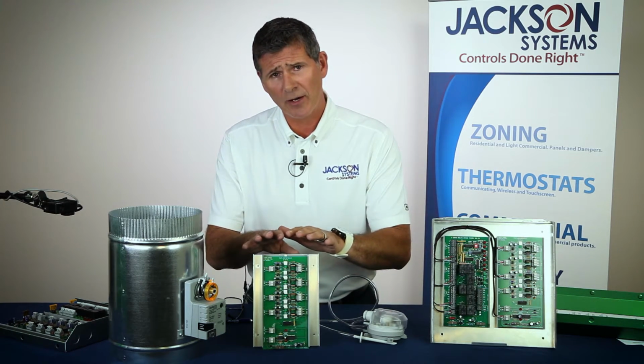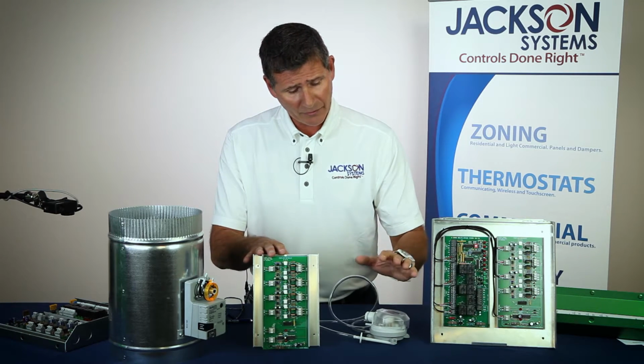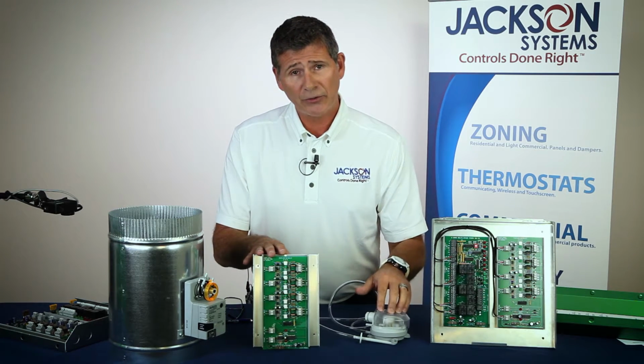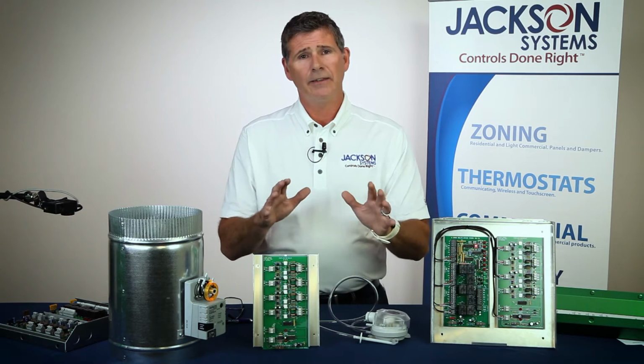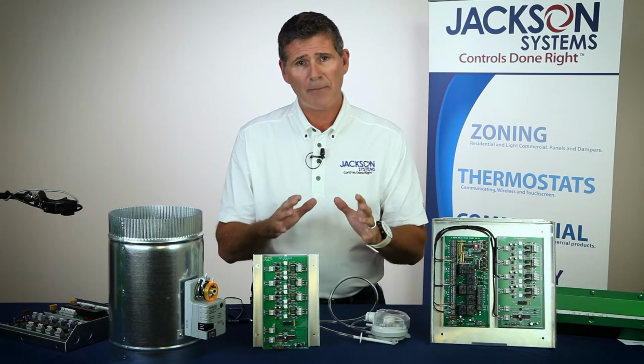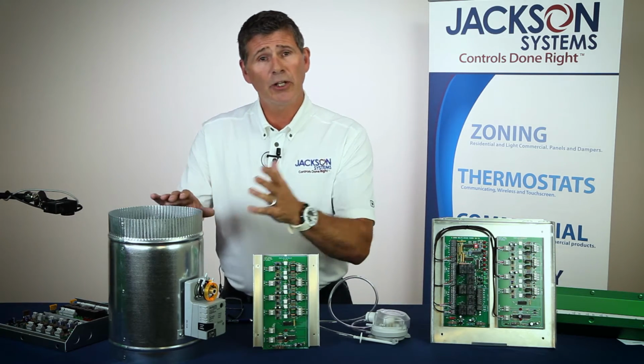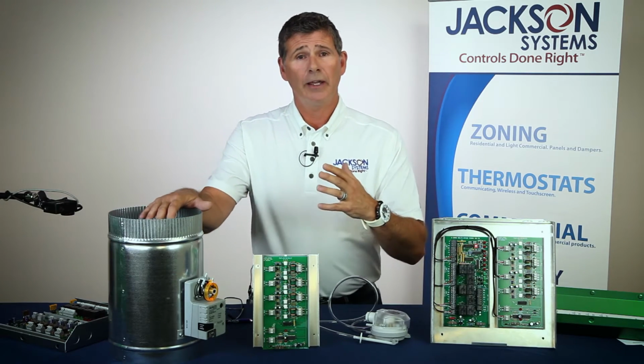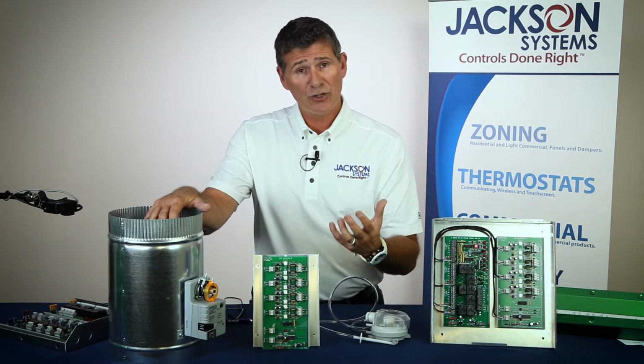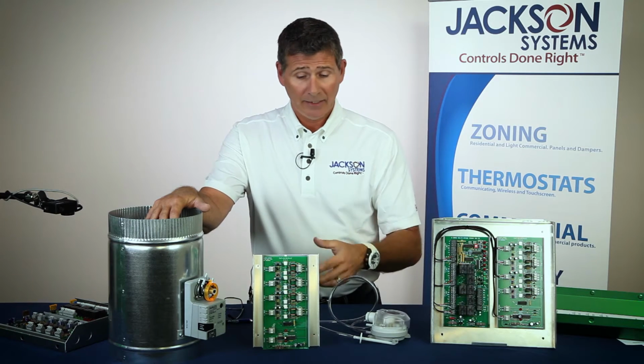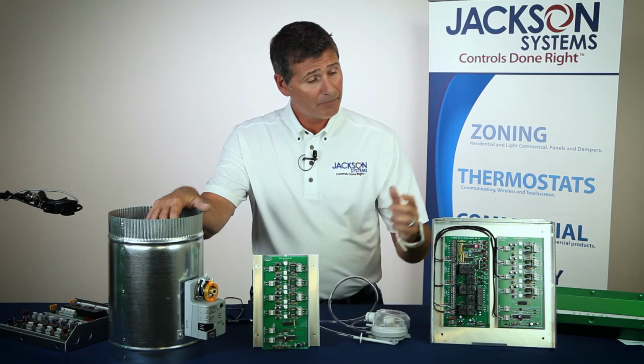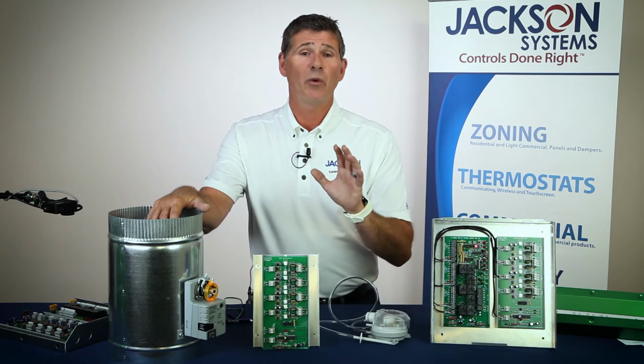The ESP, the Electronic Static Pressure Control System, with a static pressure control sensor, is going to help eliminate completely the need for a bypass system. Again, with the damper, you're going to need a 3-wire damper with a floating point style actuator. And beyond that, with the static pressure control system and our 3-zone system as well, we've got you covered.